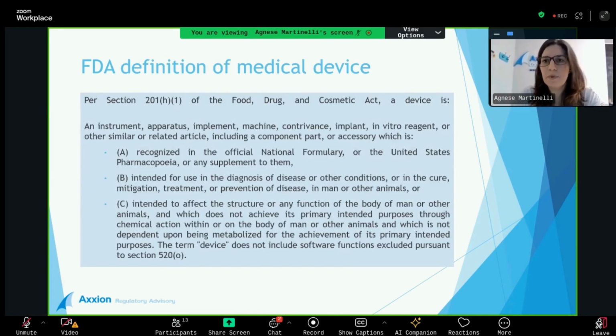So the very first step we must take is to be familiar with the medical device definition of the FDA, which has 3 main parts. It is intended for any instrument, apparatus, implement, machine, any sort of device that can be recognized in the national formulary, which has an intended use, whether it is for diagnosis, cure, mitigation, treatment, or prevention of any disease or condition. And also if it is intended to affect the structure or function of any part of the body of any human being or animal.